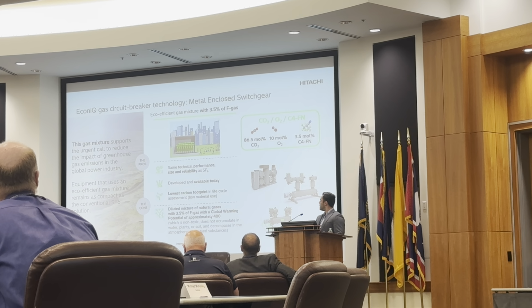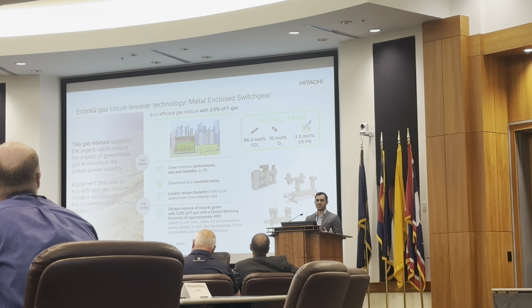Okay? And our eco-efficient gas mixture is going to be 86.5% CO2, 10% O2, and 3.5% C4FN. Because this is a very highly diluted mixture of C4FN, it's non-toxic. It's not considered toxic, it's not considered carcinogenic, it's relatively safe.